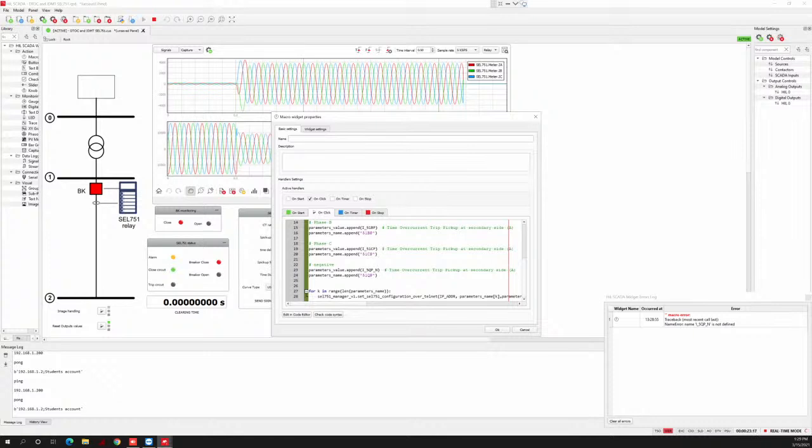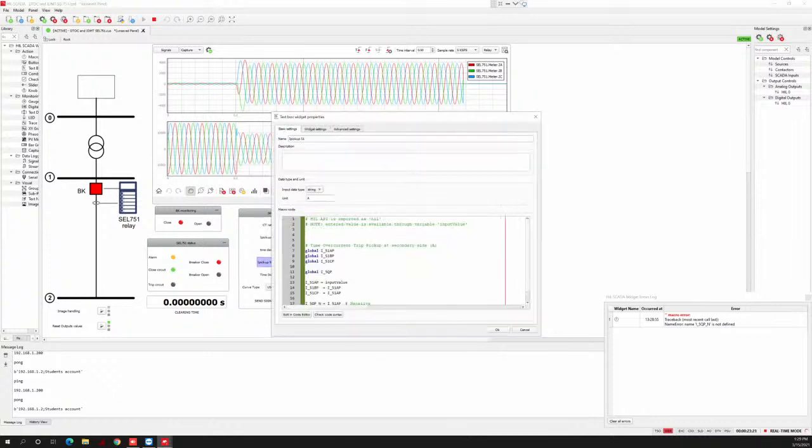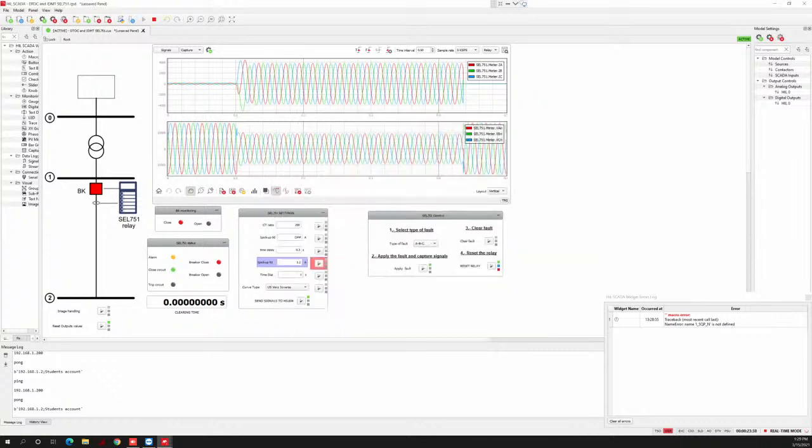Another thing is, every time that we have a fault, the device is storing the information, and it's telling you the history, what happened, when it happened, and so on. And if the device is receiving a signal from the clock, and also the device is enabled, it is able to capture the signal. I mean, the signal that you saw over there can be recorded and stored here, okay?